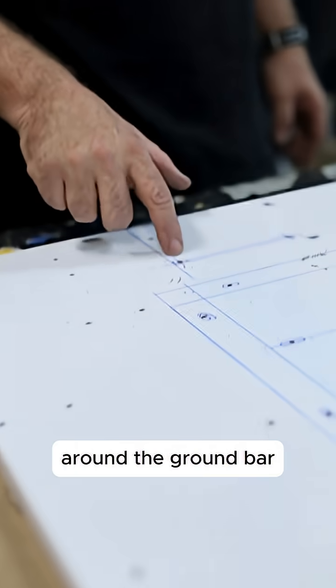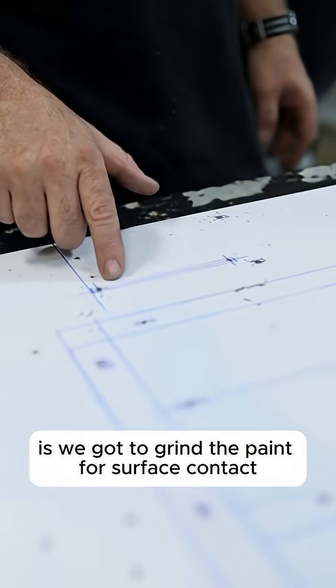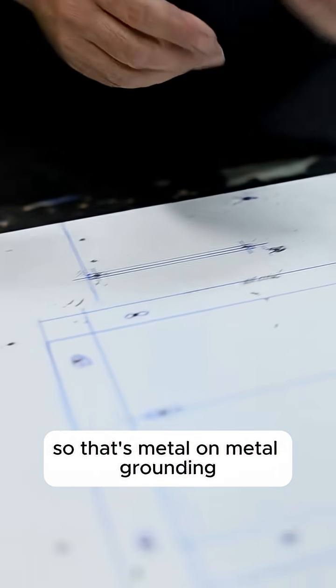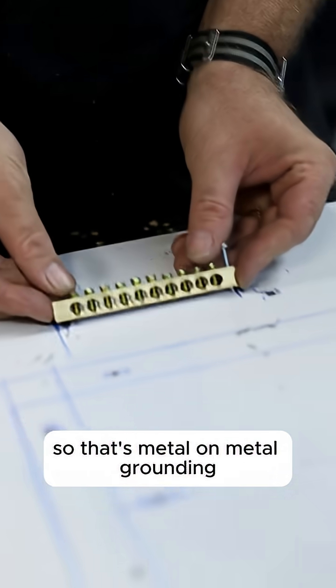The reason I drew that square on here around the ground bars is we got to grind the paint for surface contact, so that's metal on metal grounding and not metal on paint.